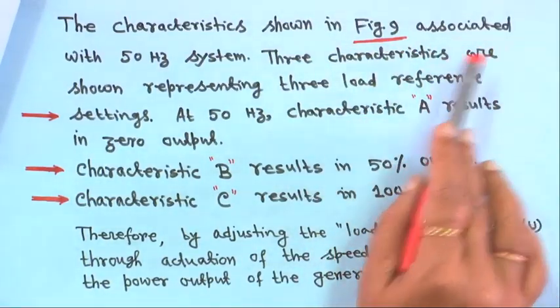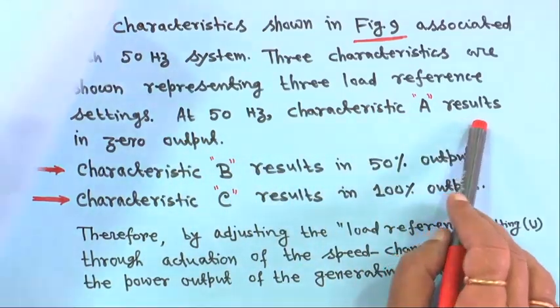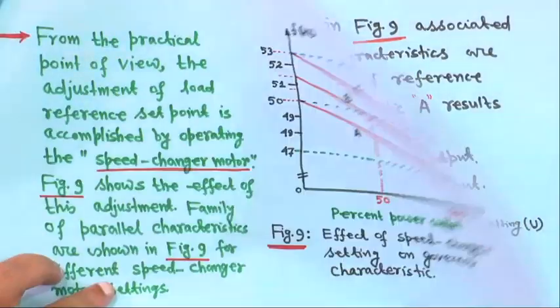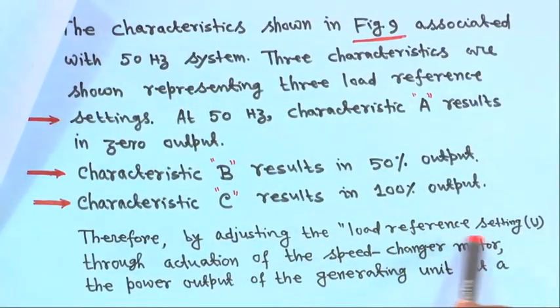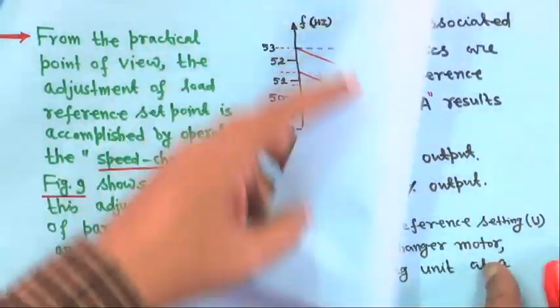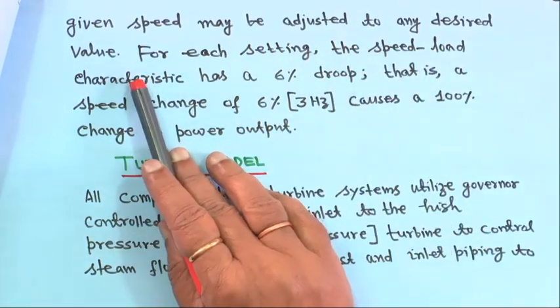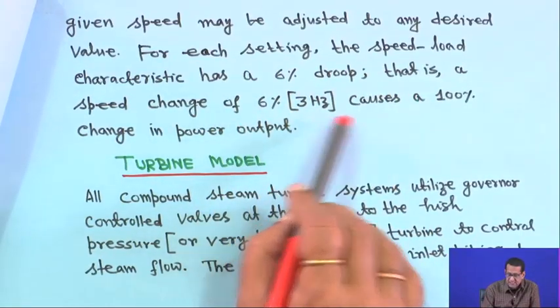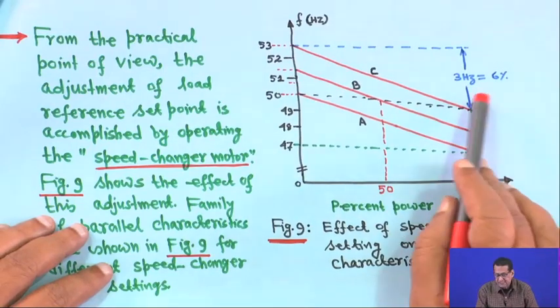The characteristics shown in figure 9 are associated with a 50 hertz system. Three characteristics represent 3 load reference settings: at 50 hertz, characteristic A results in 0 output, characteristic B results in 50 percent output, and characteristic C results in 100 percent output. By adjusting the load reference set point U through actuation of the speed changer motor, the power output of a generating unit can be adjusted to any desired value at a given speed. Each setting has a 6 percent droop — a speed change of 6 percent, or 3 hertz, causes a 100 percent change in power output.